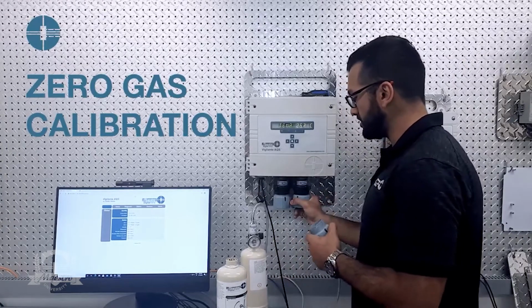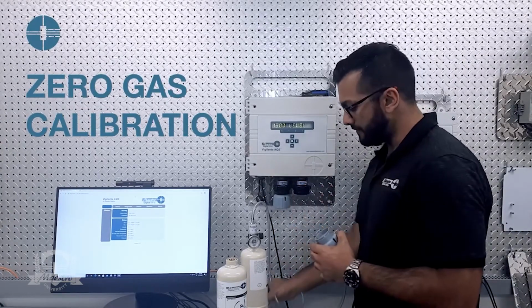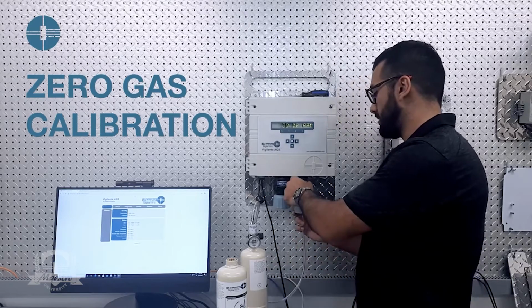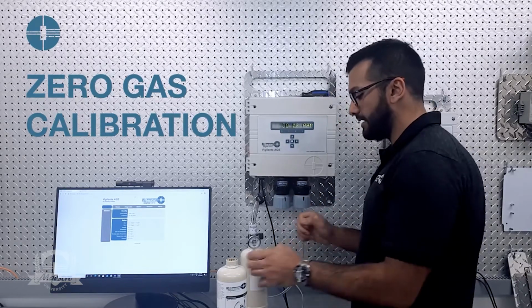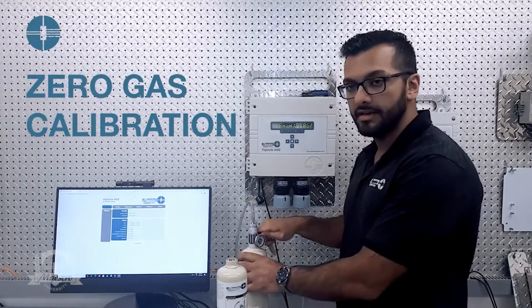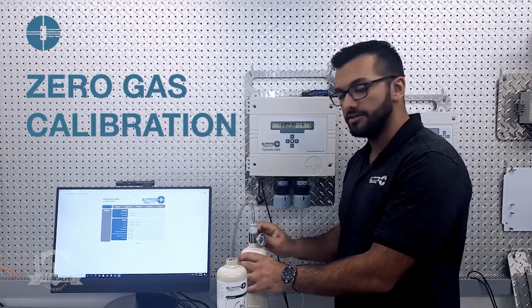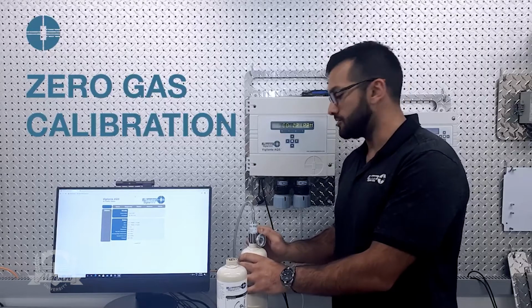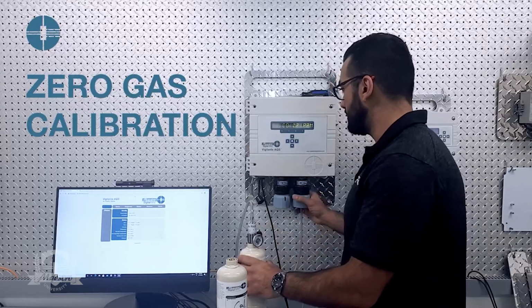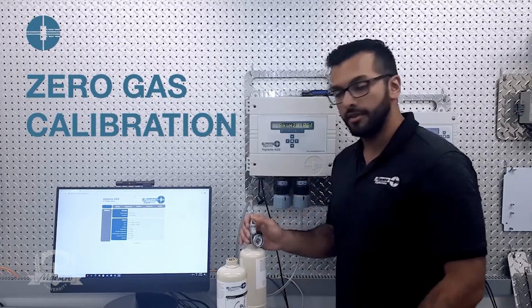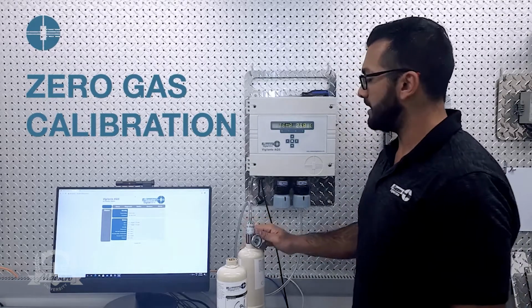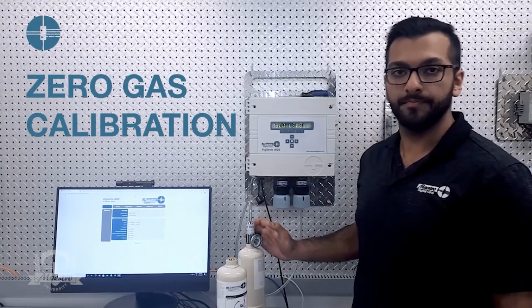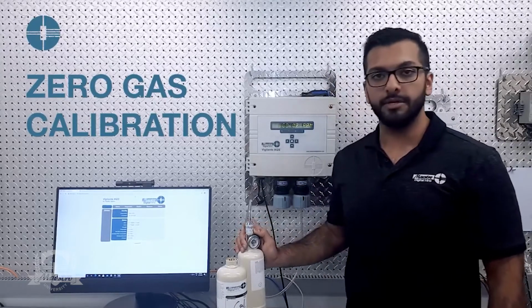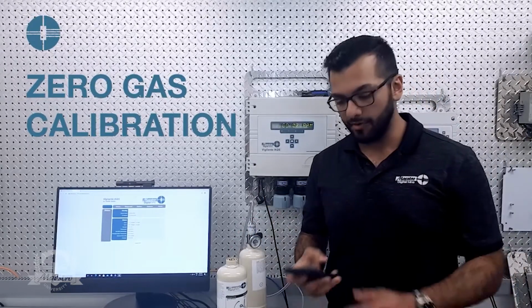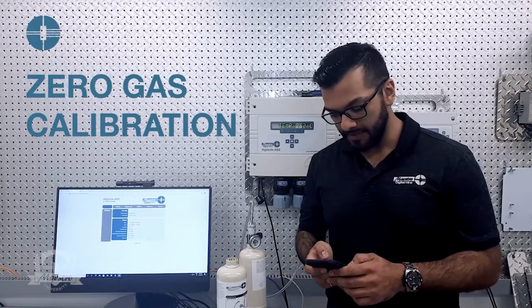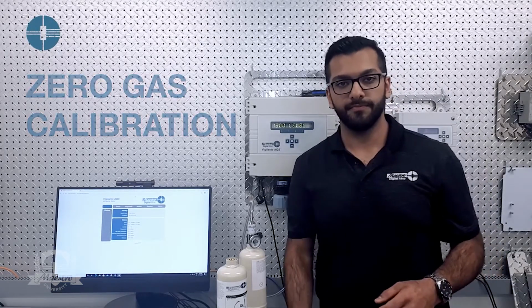So I'll take the protective cap off, plug in the calibration cup, and I like to usually start the gas just before I plug it in, just so it purges any gas from the tubes itself. And now we let this run for 3 minutes before we enter a zero calibration. So I'll be back in 3 minutes. You can set a timer on your phone to let you know when 3 minutes are over.